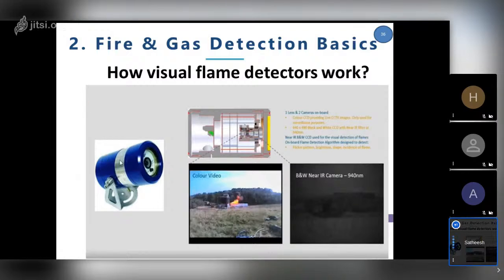Whereas the previous optical or radiation detectors—UV, IR—are looking at radiation from the fire, they don't have a camera, they cannot show it. The beauty of this device is that when detection happens, it can show the exact video, whereas those other devices can only give a signal—they are completely blind. We need to check that area to confirm whether there's a real fire or not.